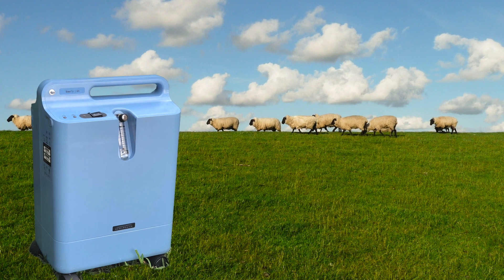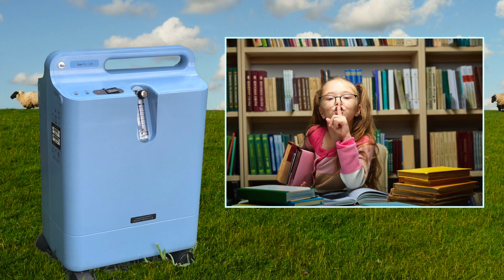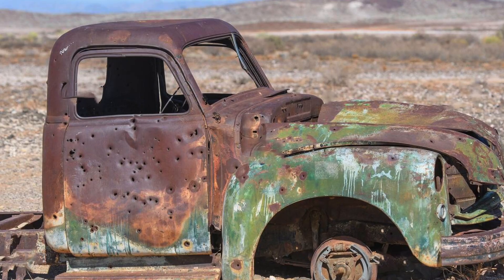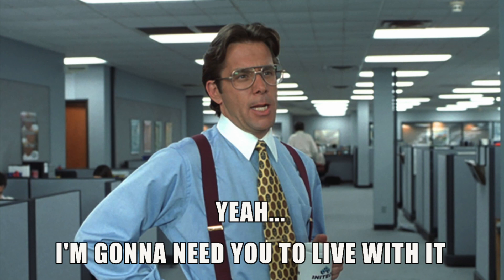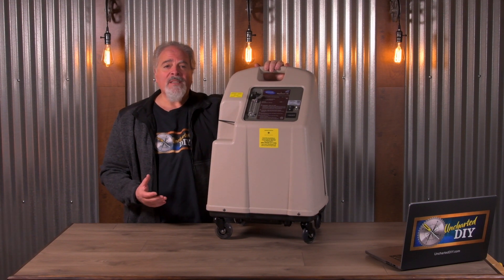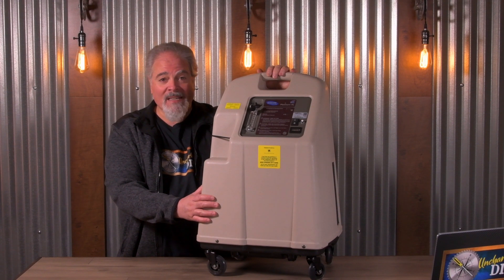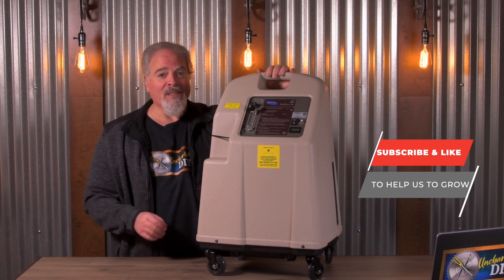Modern concentrators can be pretty quiet. Some of the more expensive models have sound levels as low as 37 decibels, which is as quiet as a whisper in a library. But many of us are stuck with old, poorly maintained machines rented from a durable medical equipment or DME provider. The quality of these concentrators from DMEs varies, but some companies are abysmal when it comes to maintaining or replacing provided machines. As these oxygen machines accumulate usage hours, they can become really noisy, and the providers will usually just tell you to live with it. Since you can't make permanent changes to these rented concentrators, I'll show you some ways to help quiet them down without getting in trouble with your provider. The machine I'm working on today is an Invacare Platinum XL, though these same tricks will work on pretty much any concentrator, though you might need to make some modifications to fit your particular situation.